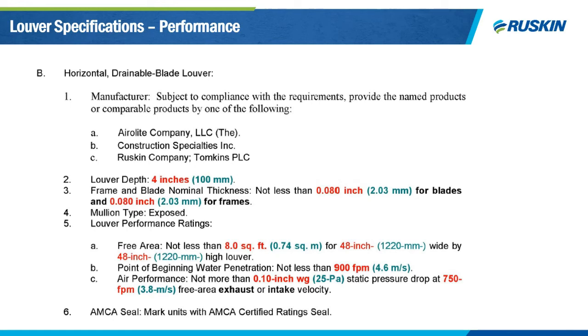Here we have an example of a spec that's not written around a specific model. Rather than using performance unique to a particular model, it uses rounded number values based on the actual requirements of the job. These numbers are easier to review and easier to type into software to compare to other models. Note that the pressure drop is 0.1 inches at 750 feet per minute free area velocity — most likely what the actual design airflow is for the job. This spec is no less demanding performance-wise than the previous spec, but it's laid out in a way that's easier to analyze and less daunting for those who are bidding the job. If you're typically using guide specs specific to models, this type of spec requires additional legwork up front but could result in a more competitive bid and reduce your overall costs.